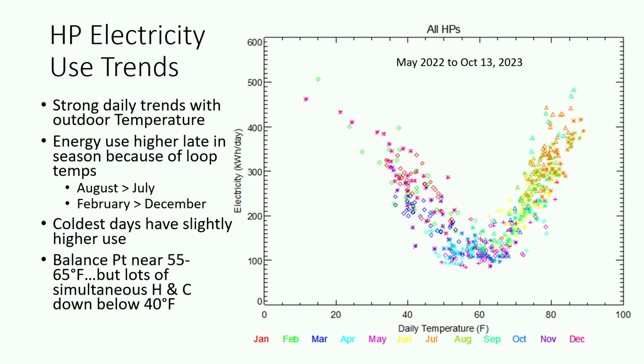The balance point for the space heating seems to be about 55 or 60 degrees. By the time you get to 40 degrees, the simultaneous heating and cooling has gone away and you're all heating. We also see what you normally expect in a geothermal system. Late in the summer, loop temperatures are a little hotter, so energy use is a little higher. Late in the winter, the incoming temperatures are a little colder, and therefore the energy use is a little higher. Basically, this is all the things we expect to see on a geothermal loop.